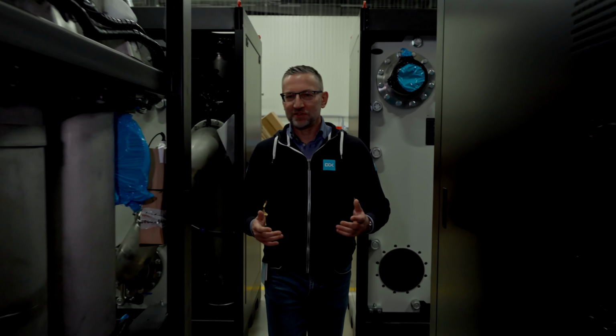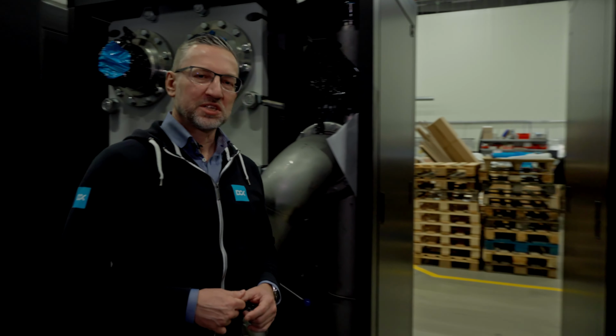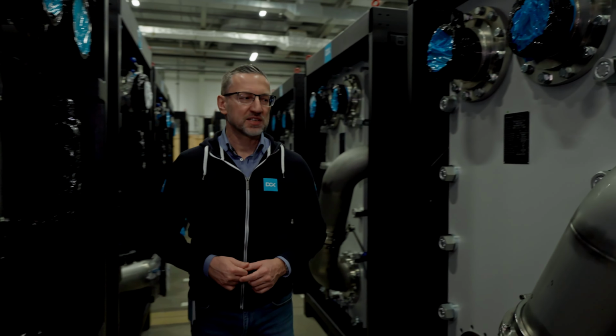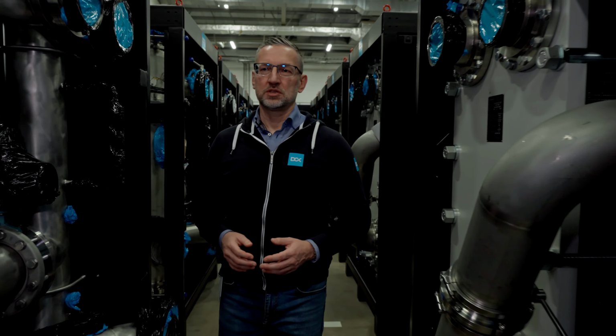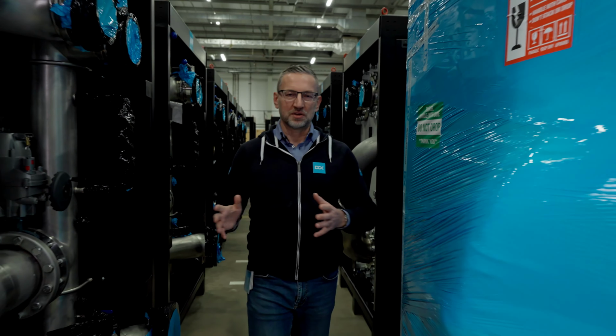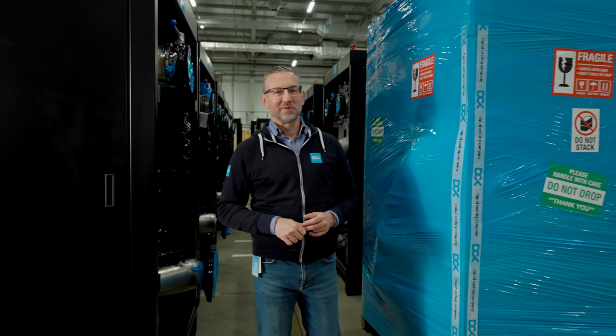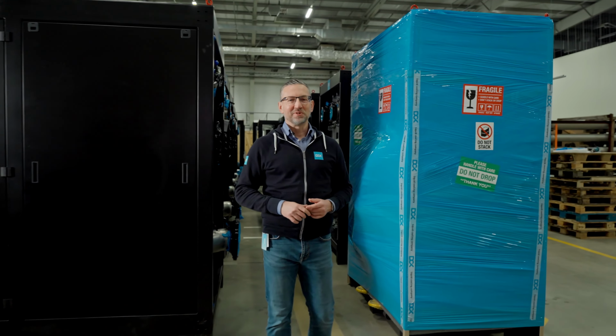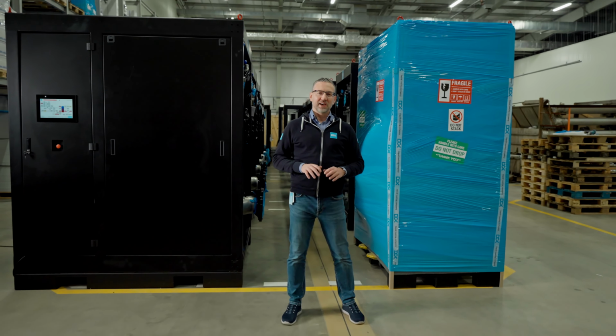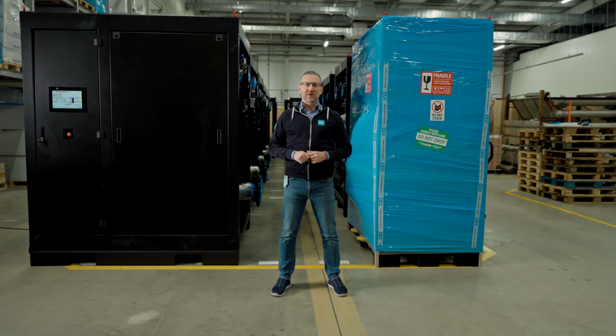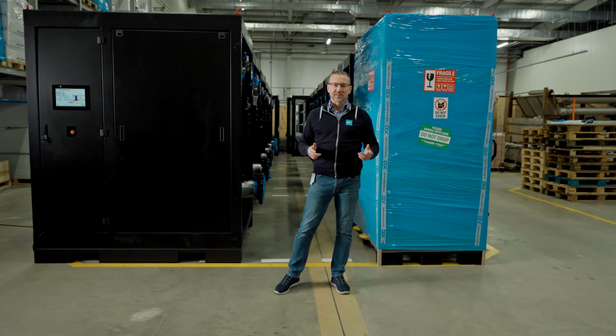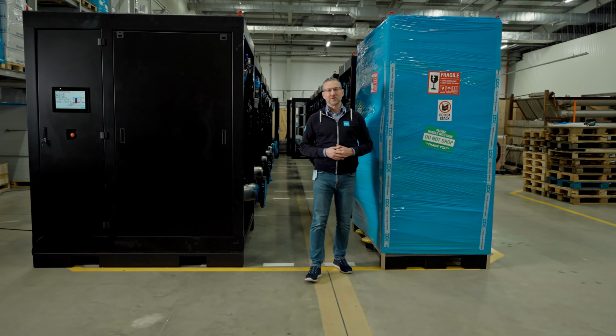Right now we are shipping approximately 50 of those CDUs, or FDUs as we call them, to customers in Europe and in the US. They are the most capable ones. They are designed for hyperscale, so we have hyperscale customers. And if you have the same application, you need to deliver AI in limited time, you cannot wait 50 or 60 weeks for those small 1 megawatt CDUs and integrate hundreds of them, please let us know. We'll design the cooling loop, we'll support you on every capacity, and we can provide those CDUs in approximately 20 weeks if we can prepare for your order.